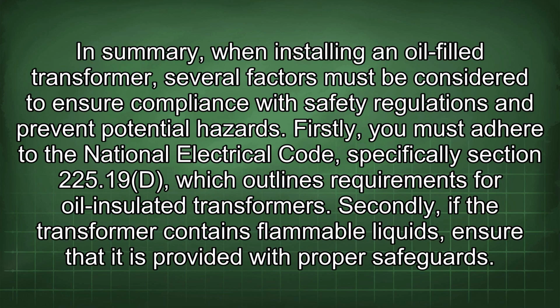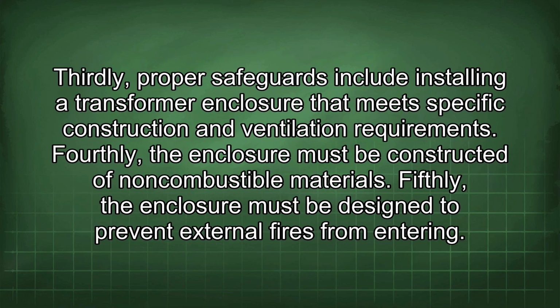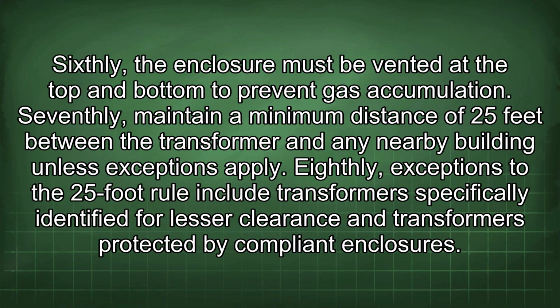In summary, when installing an oil-filled transformer, several factors must be considered to ensure compliance with safety regulations and prevent potential hazards. Firstly, you must adhere to the National Electrical Code, specifically Section 225.19d, which outlines requirements for oil-insulated transformers. Secondly, if the transformer contains flammable liquids, ensure that it is provided with proper safeguards. Thirdly, proper safeguards include installing a transformer enclosure that meets specific construction and ventilation requirements. Fourthly, the enclosure must be constructed of non-combustible materials. Fifthly, the enclosure must be designed to prevent external fires from entering. Sixthly, the enclosure must be vented at the top and bottom to prevent gas accumulation.